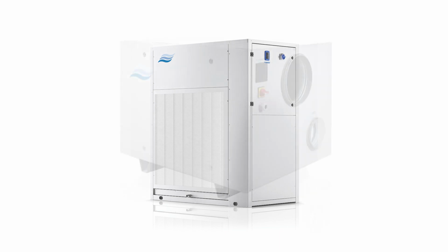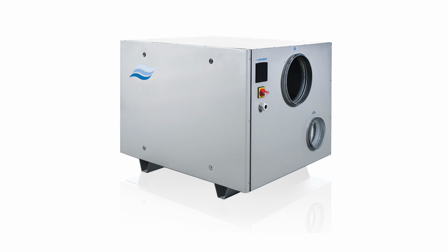And in fact, desiccant dehumidification results in even more heat gain. This is because in a desiccant dehum, a heater is used to blow hot air through a section of the desiccant rotor. Now, this removes the absorbed water from the desiccant rotor and blows it outside via ducting. Now, the residual heat from this rotor regeneration process will add even more heat to the process airflow than is already happening from the thermodynamic process. So both types of dehum will add heat when drying, but the desiccant unit can add significantly more.